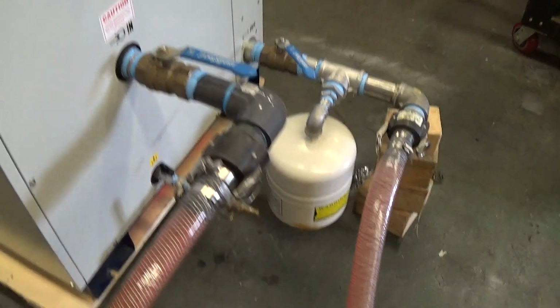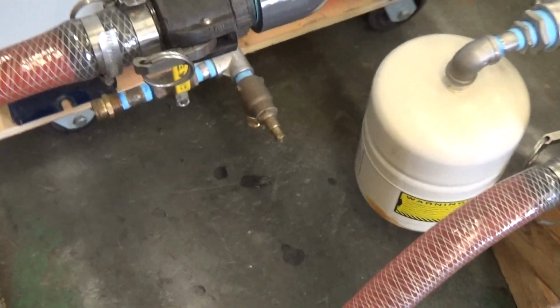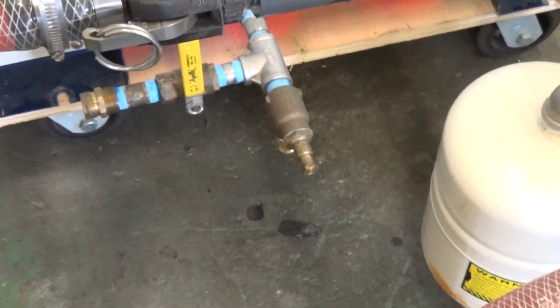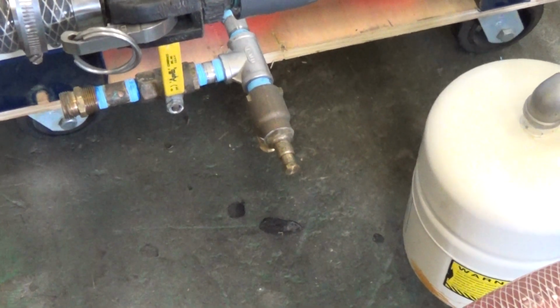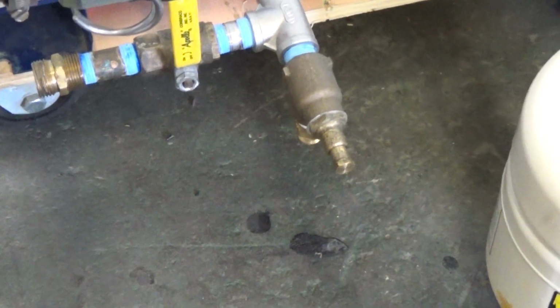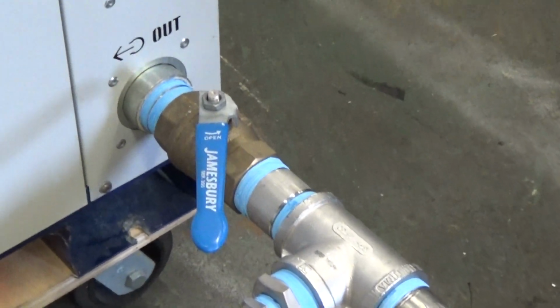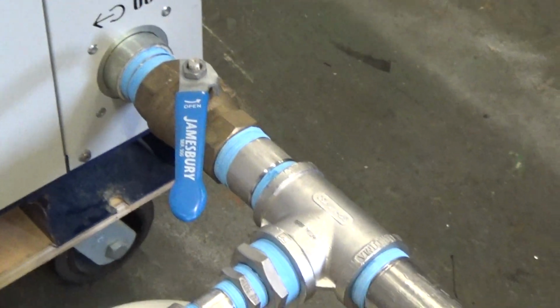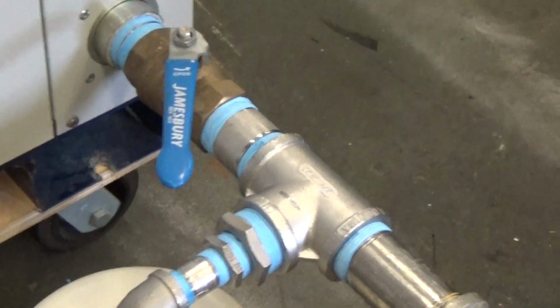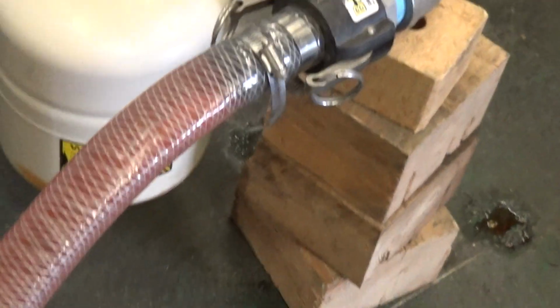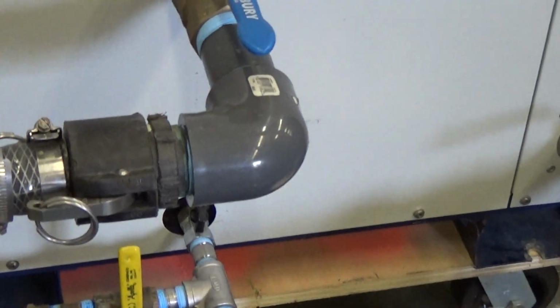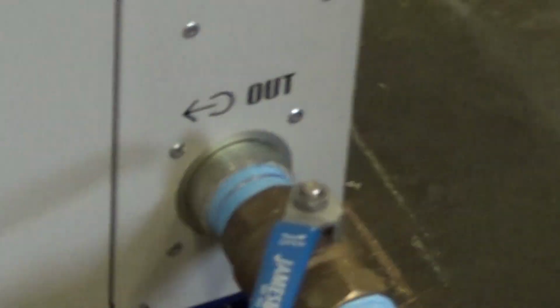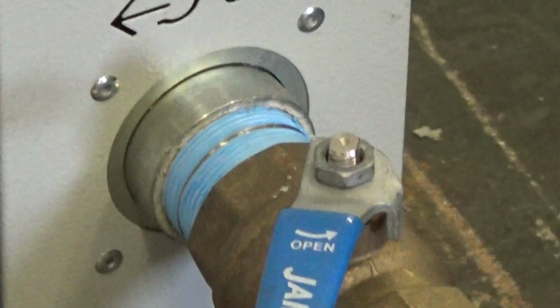And what's going to ship with the chiller, for whatever reason, this bypass valve came in on the drain. We're going to ship it loose in a box. But that pressure relief bypass, as a safety, you normally would put here on the outlet of the chiller. For our loop here, we just set up a glycol loop from the inlet and the outlet. That's the return or in. That's the out.